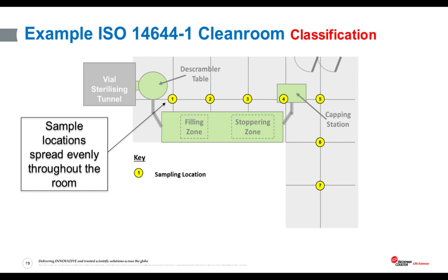Here is an example of a clean room — not meant to be prescriptive. You can see how the ISO standard tells the user to calculate the correct number of locations according to the size of the clean room, and then lay the sampling locations out in an evenly distributed grid pattern across the room. According to the ISO standard, there is no requirement to take a sample where the product is at risk of airborne contamination, because it's just checking the room itself. In this example, following the ISO standard means no samples are taken where a product may be at risk — for instance, at the de-scrambler table, the filling zone, the stoppering zone, or the capping station.